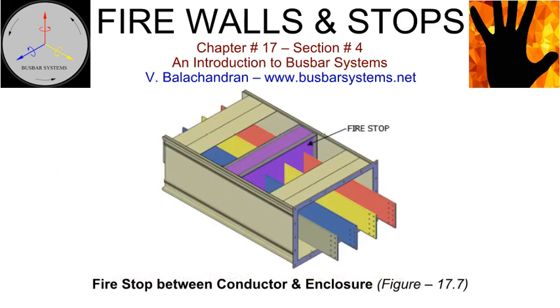Fire partition between conductor and enclosure. The process of preparation of the fire stop inside the metal enclosed air-insulated bus enclosure is very critical. The preparation of the conductor insulation at this location is very important. The conductor shall be fully insulated for the specified thermal class, basic insulation level, and creepage distance.